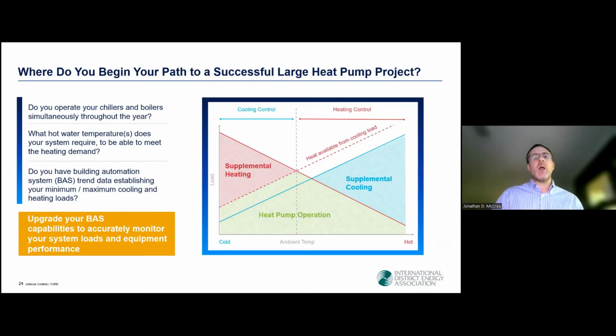Just what can you tolerate on a winter design day and still satisfy the requirements of the spaces that your system serves? You can always use a hot water reset strategy, and we certainly encourage that during off-design conditions. But ideally, you want your heat pump to be capable of producing a hot water temperature that's usable pretty much any day of the year. So let's assume that you have determined that you can live with 170 degrees supply hot water temp.